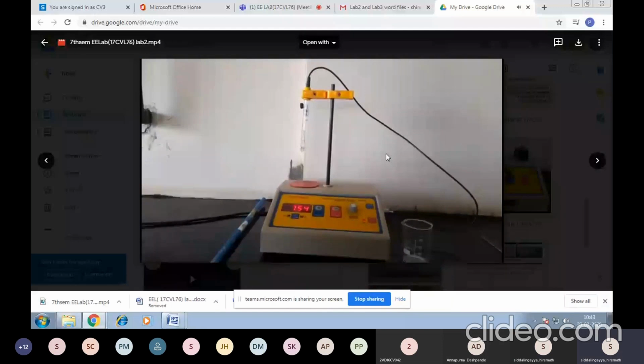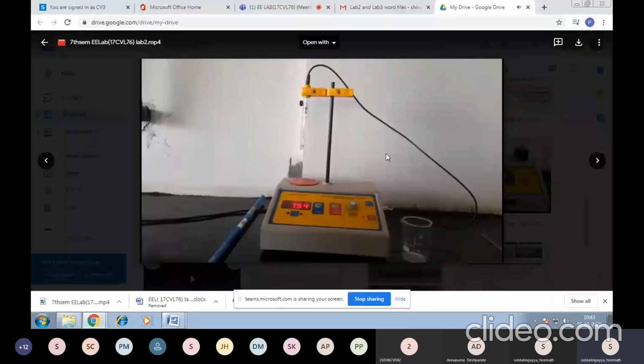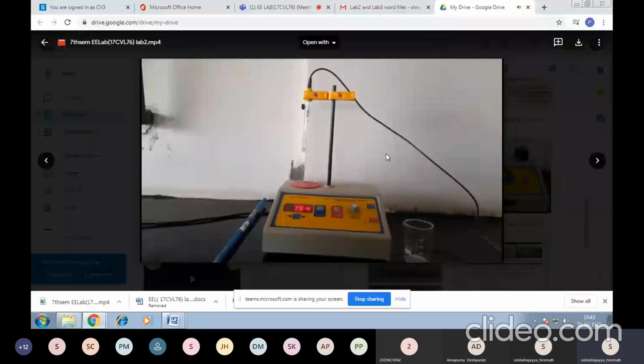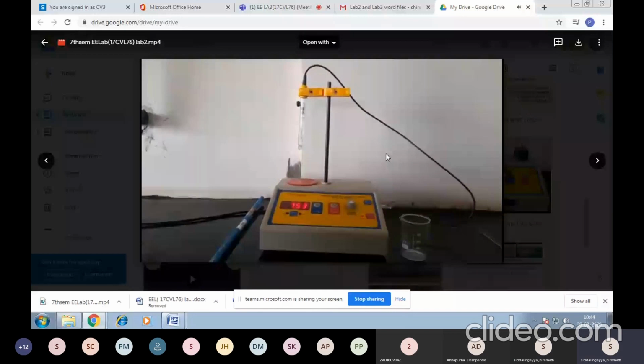At pH values above 10, so-called alkali errors may occur. In such cases, the use of an alkali-resistant electrode is recommended. Change in glass structure can occur in older electrodes, so that errors may appear when measuring weakly buffered water. In such cases, the electrode should be renewed.